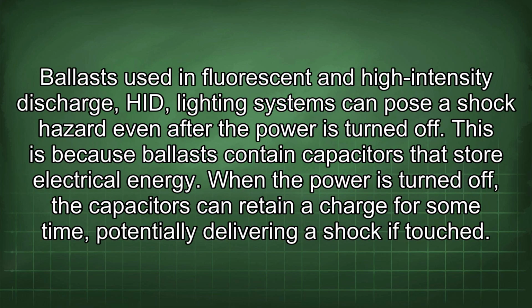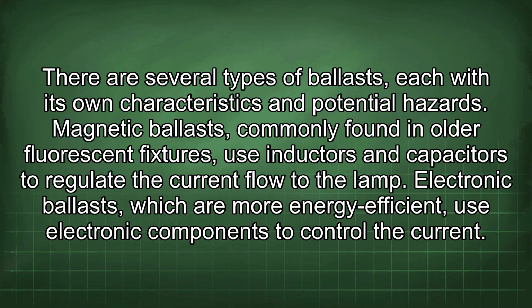Ballasts used in fluorescent and high-intensity discharge, HID, lighting systems can pose a shock hazard even after the power is turned off. This is because ballasts contain capacitors that store electrical energy. When the power is turned off, the capacitors can retain a charge for some time, potentially delivering a shock if touched. There are several types of ballasts, each with its own characteristics and potential hazards.